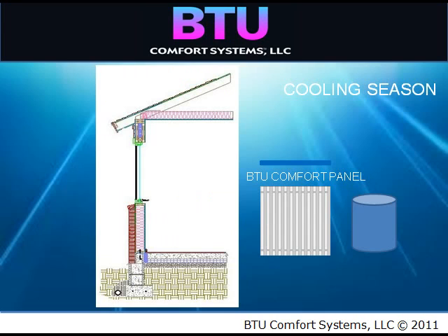Let's take a look at what happens in the cooling season with panels placed at the ceiling. Hot air rises and is absorbed by the cool panel surface. In turn, the embedded tubing with cooled fluid running through it absorbs this heat and transfers it out of the building. Cooled air begins to fall towards the floor. This cycle repeats over and over, silently providing cool comfort. Each zone can have its ideal temperature set for the comfort level desired.